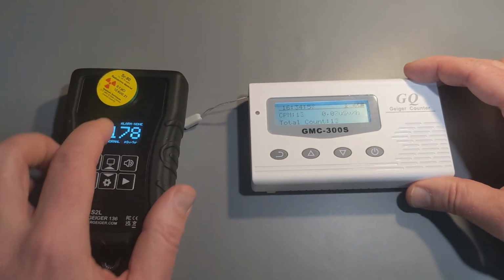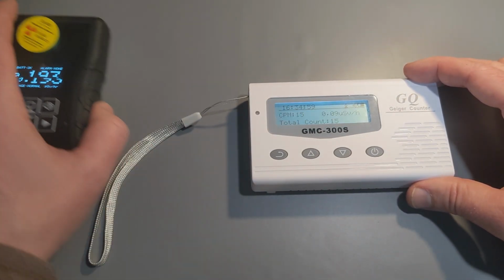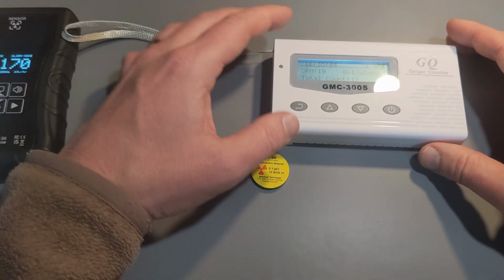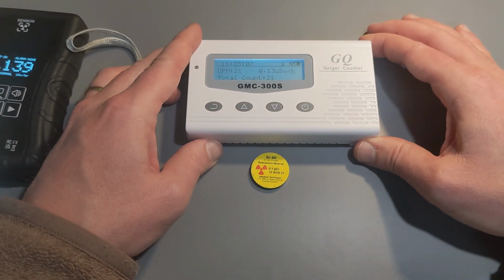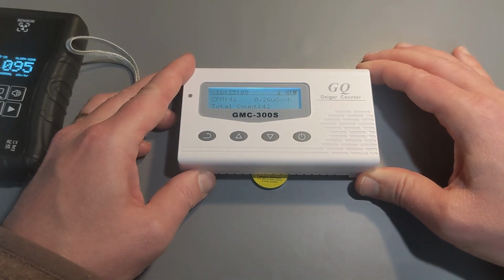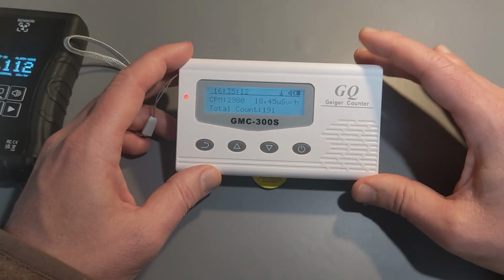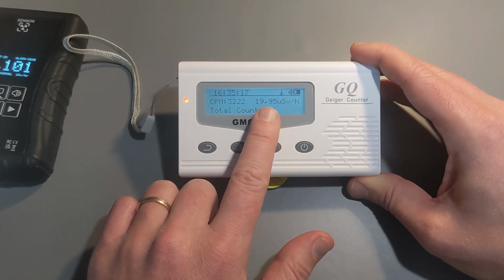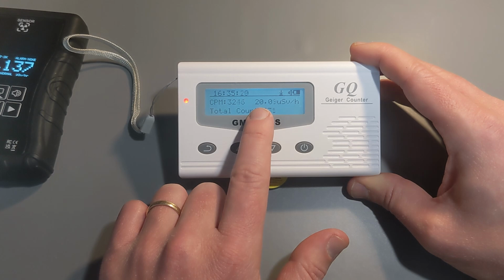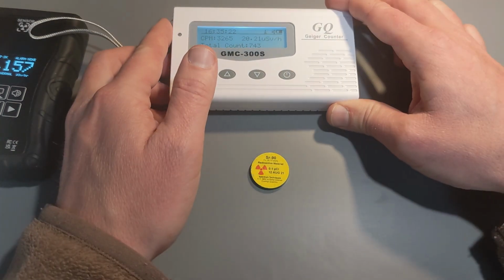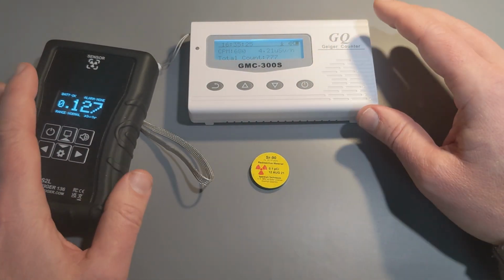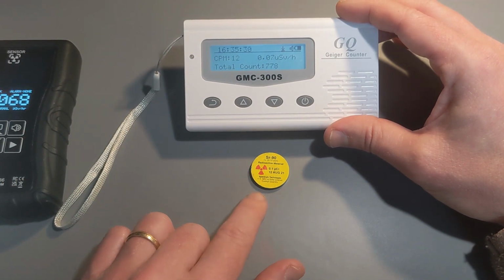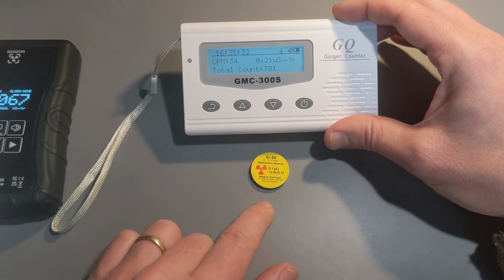And when I put the beta source there, it correctly shows still a quite low dose rate, because it's not a penetrating radiation type, and it should mostly be neglected. So the risk is, if you have something that's emitting a lot of beta and you use a typical low-cost Geiger tube detector, you'll see the count rate goes up and the dose rate goes up quite a lot. So here you have about 20 microsieverts per hour, and they were both measuring around, let's say, 0.1 or so in the background. That means this was overestimating the dose rate by a factor of 200.